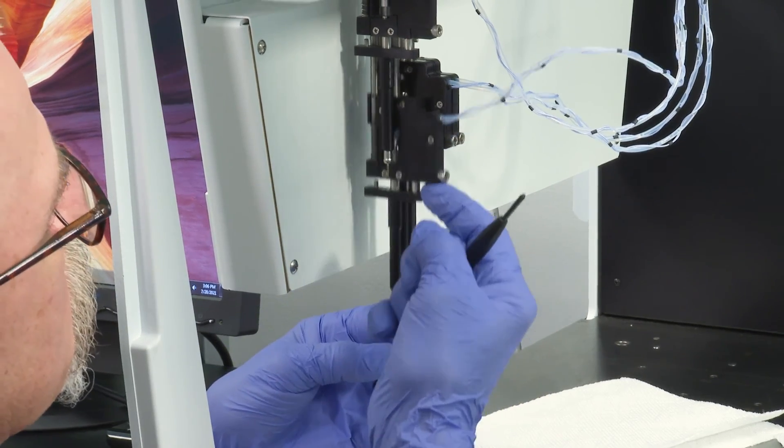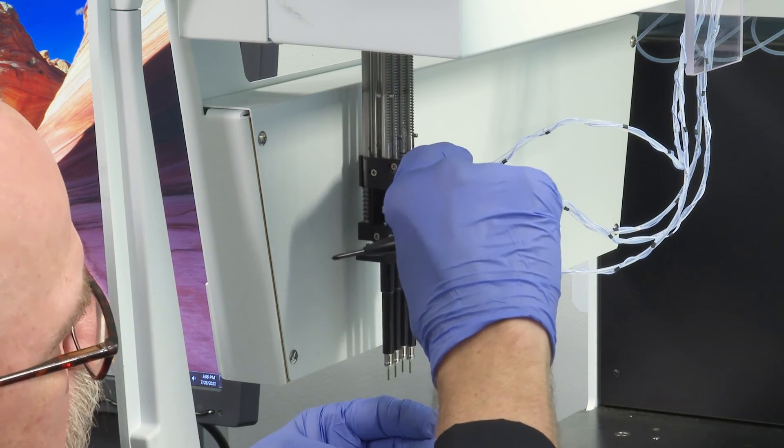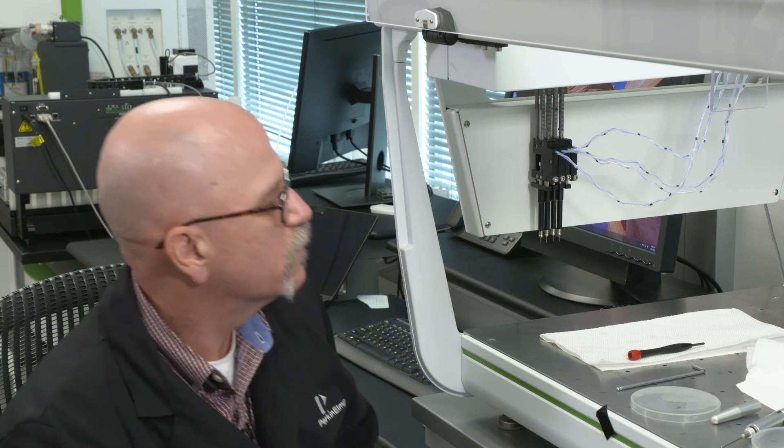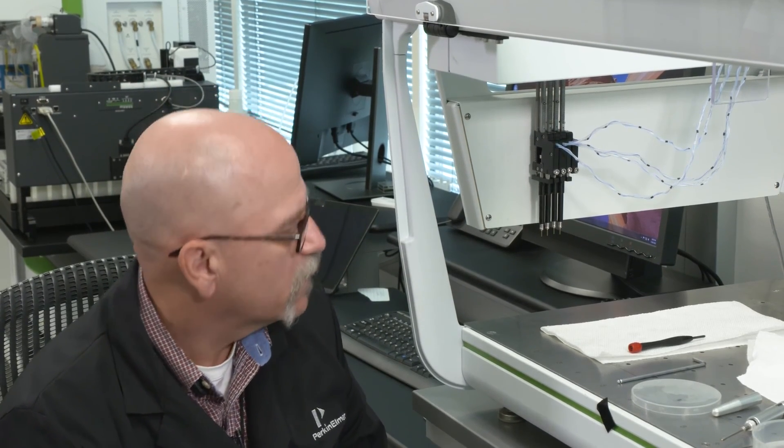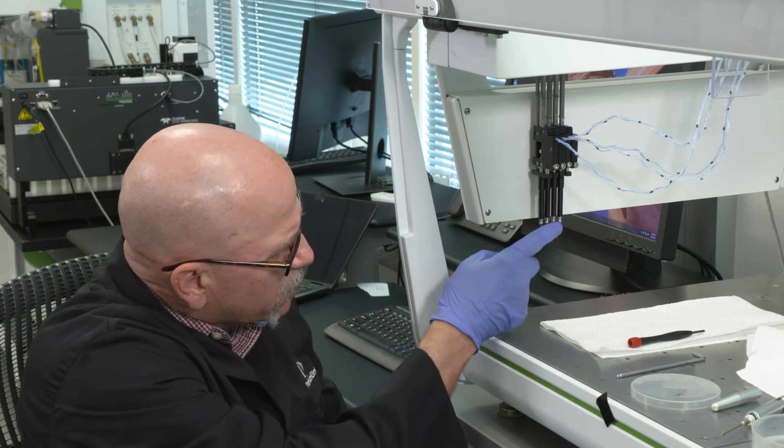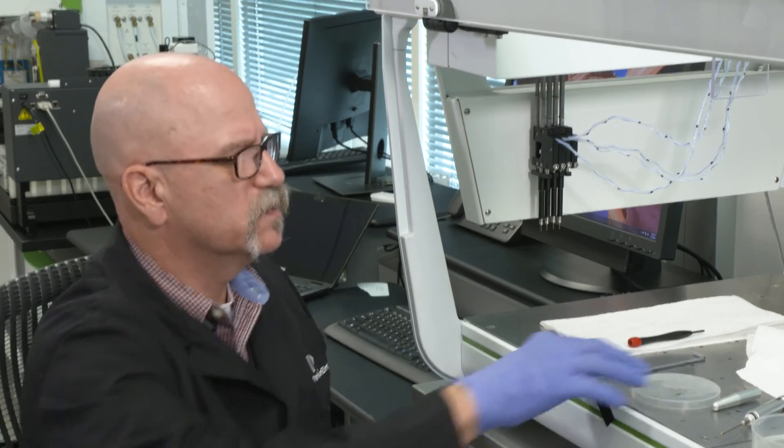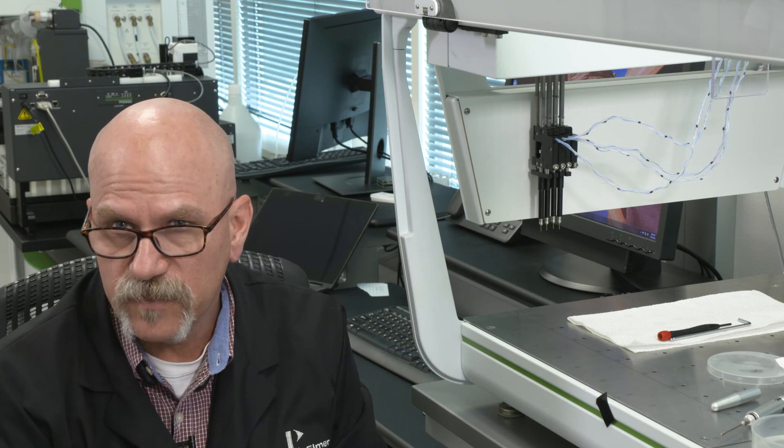And you restart your instrument and initialize and check it by running and looking at the engagement to your tip boxes. And you can also use a tip alignment tool that's in your special tools kit to give a basic idea of your alignment. That concludes replacing the Z-Rack.